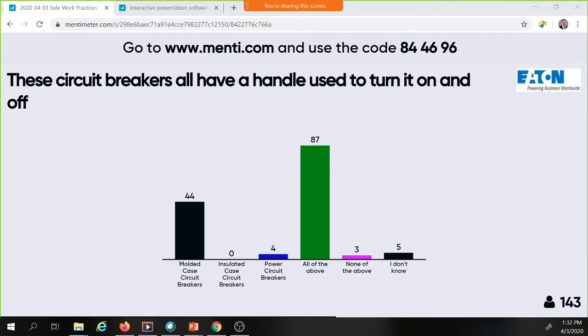Molded case circuit breakers, 44 respondents. I had 143 respondents said a molded case circuit breaker. They all have a handle that's used to turn it on and off. Power circuit breakers, I got 4. 87 people said all of the above. I mean, why wouldn't you have a handle to turn off an overcurrent protected device, right? You have to turn it on and off. And what do we do? We turn the light switch on and off. We use a handle. Why wouldn't you do that for all circuit breakers? I mean, it seems like a logical answer. So those 91 of you, I love you so much, but you're wrong.